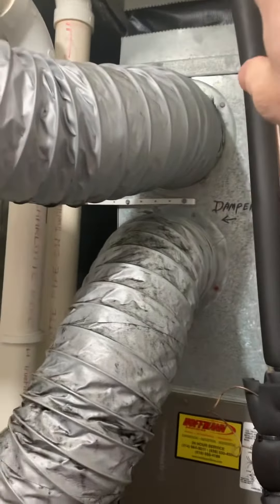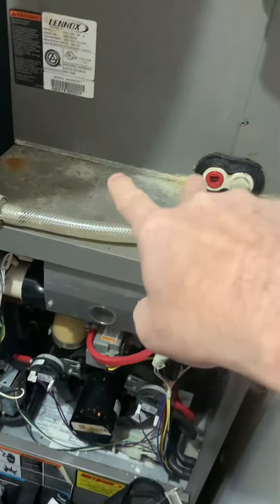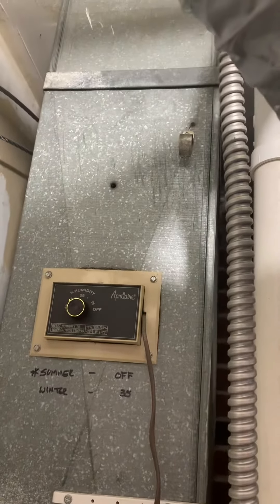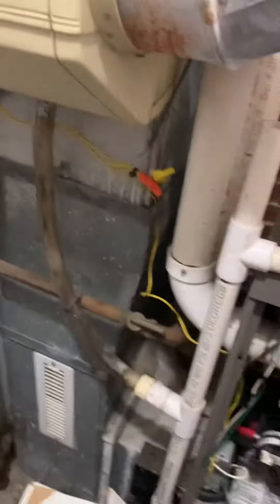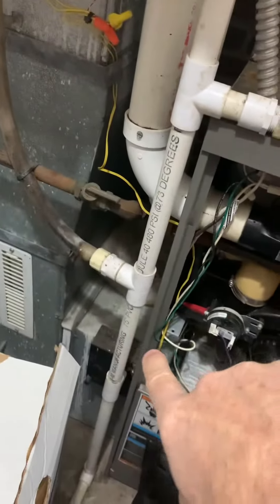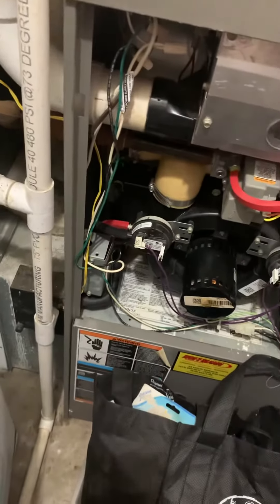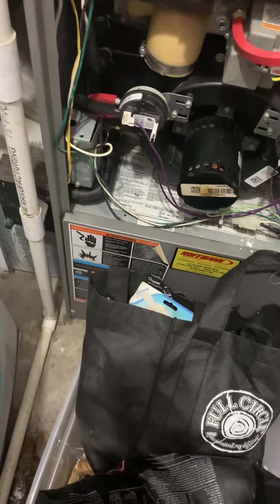We'll have both of those come off of there and bring the piping down into the furnace. We'll modify the line set — it'll cut and flush here. On the return drop, there's a slip and drive — this is 10 by 24. We're looking at replacing this; we shouldn't need the offset anymore. This is eight inches and we only kick over about an inch, so we'll be able to get our filter in here.